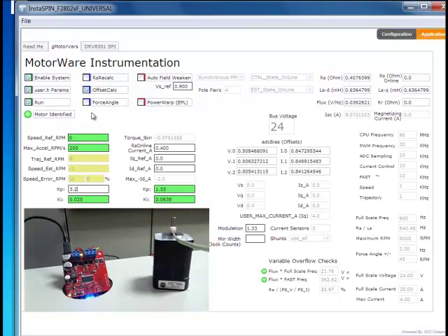In the user's guide, it mentions turning on force angle if you're trying to start up. And that's a good path to follow, especially if you have a load. It's going to give you a more consistent startup. It will start up even without force angle on. It will attempt, and as soon as FAST locks on and it gets moving enough, it will take over and be able to drive it typically to your speed.